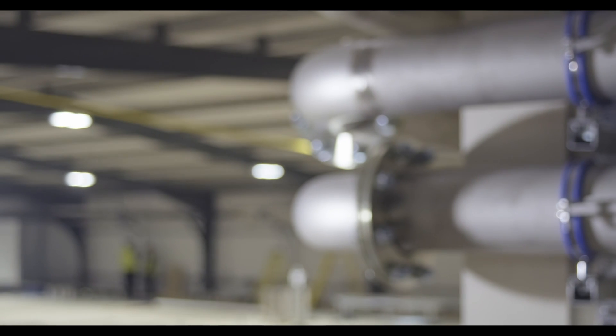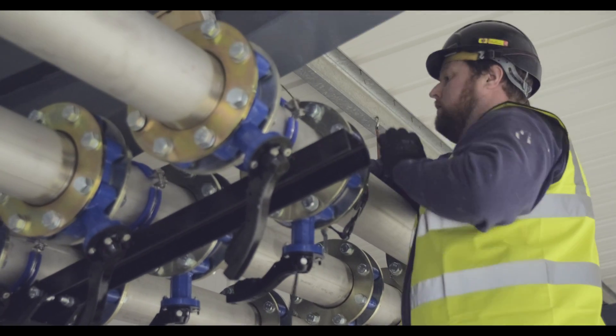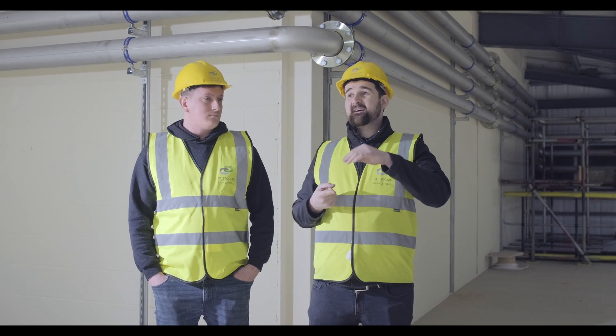We've had a few questions on the previous video regarding the use of chillers over the evaporative cooling we use at Maidstone. One of the main reasons is we're actually in very close proximity to the M25, specifically the Dartford Crossing - about a third of a mile away - so there were quite large concerns regarding pollution. Evaporative cooling works best when using large amounts of fresh air through the room, so we'd need to come down to F7 filtration with a G4 pre-filter and F7 final filter. With the levels of pollution in this local area, we'd be going through a lot of filters keeping the air clean.